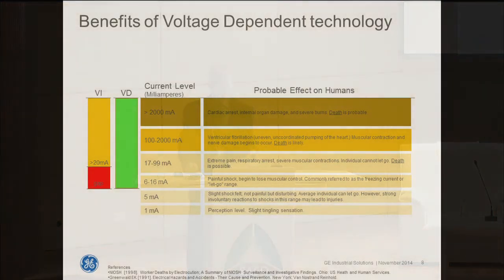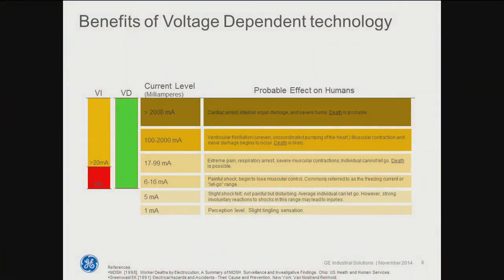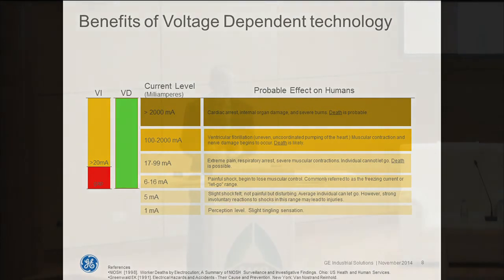And the 6 milliamp threshold is where those effects just start to become really perceptible, and the human can still release themselves from an electric shock. If you look at the 20 milliamp level, you start to get into a zone of extreme pain, possible respiratory arrest. And so that level is relatively high. It won't necessarily cause death. It may or may not, depending on perhaps some other conditions of the human body.